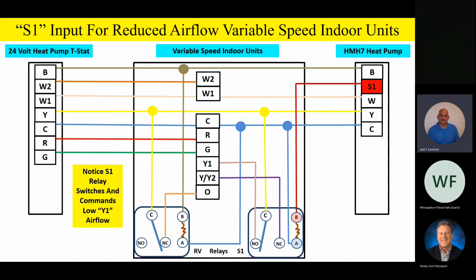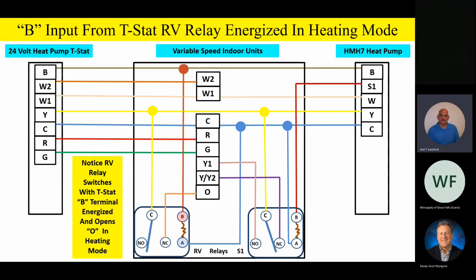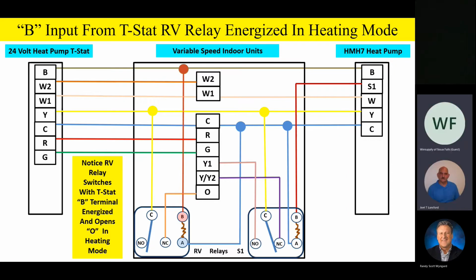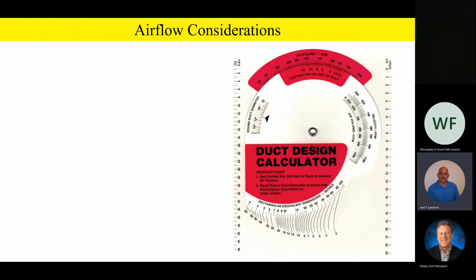Let me do that one more time. Watch the animation. When we go into the heating mode of operation and we energize the B terminal for a reversing valve, bang, we switch that RV relay and we break that O signal. And what that does, it tells the indoor unit that we're in the heating mode of operation now on that variable speed indoor product. Any questions or comments on the relay logic of the RV relay and the S1 relay for airflow reduction and how all that works? No, I think we're pretty clear. You went over it pretty well, so it cleared up my questions on it. Okay, good, excellent. Well, fellas, with that, let's go ahead and take a look.